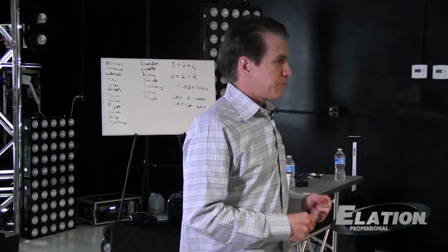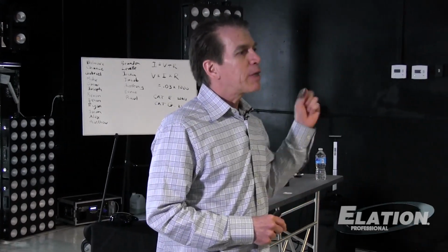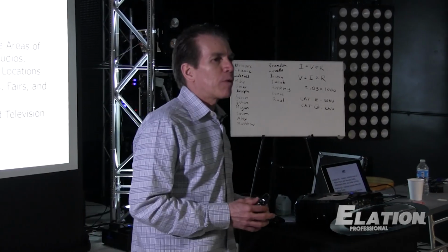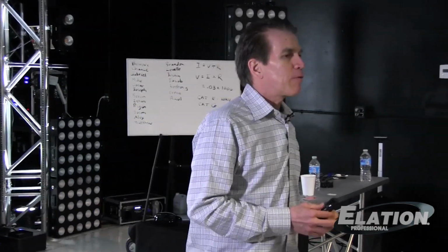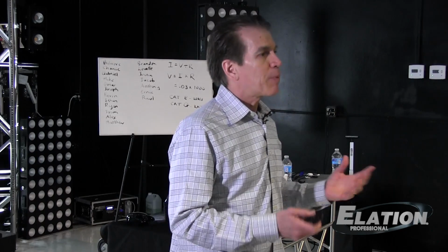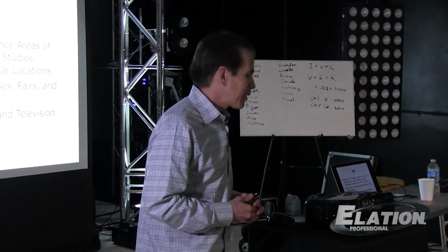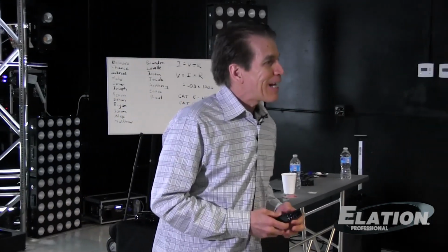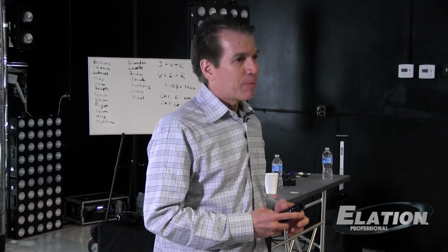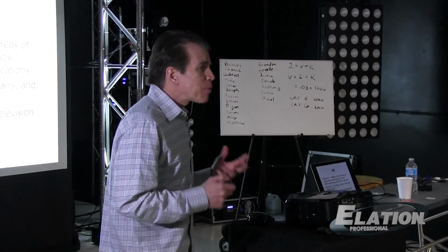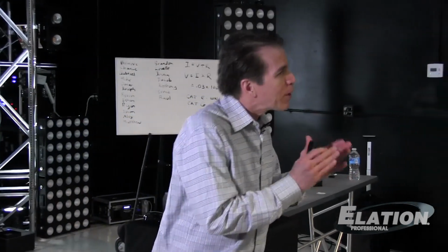A friend of mine in Austin is putting in a kind of museum in a planetarium. And he was having trouble with the local inspector. And I got a phone call from him, and this was with regard to the Socapex cable. So I told him to look in Article 520, but in the end, that Socapex cable is not listed, so they had to change it out. But anyway, the important point is, it helps to know the code, to know where to go to figure out where things apply.